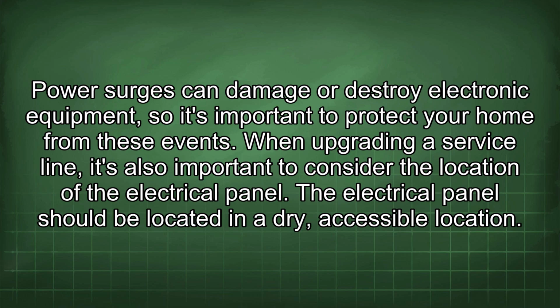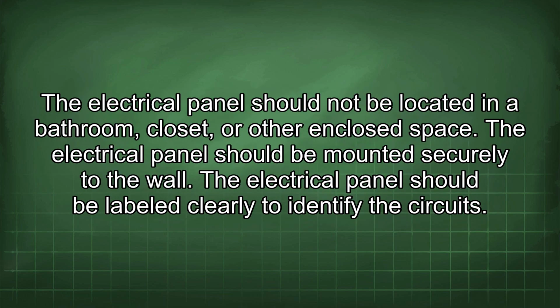When upgrading a service line, it's also important to consider the location of the electrical panel. The electrical panel should be located in a dry, accessible location. The electrical panel should not be located in a bathroom, closet, or other enclosed space. The electrical panel should be mounted securely to the wall. The electrical panel should be labeled clearly to identify the circuits.